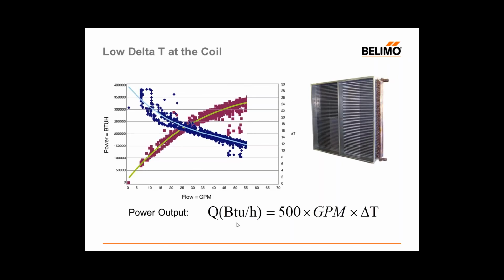So on the right side, we have increasing delta T readings in degrees Fahrenheit, and you can see that the delta T has sort of an opposite performance, but for the same reason as the coil. So remember, at low flows, our water was sitting for a long time in the coil and was transferring heat more efficiently, and therefore we have a higher delta T. As we push the water faster, we're going to be less efficient and have lower delta T.